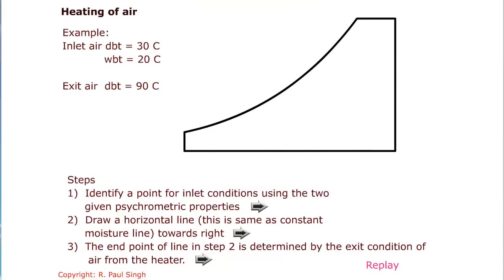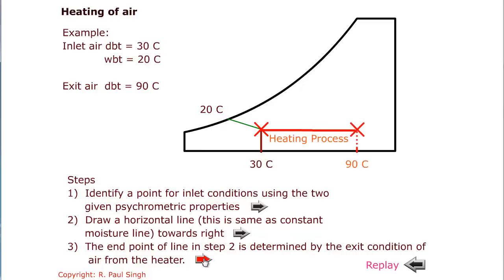Let's look at some animations. In the case of heating of air from 30 degrees C dry bulb temperature and 20 degrees C wet bulb temperature, we identify a point and then follow a horizontal line to the final exit air temperature of 90 degrees Celsius. Thus, we have identified the horizontal line and the initial and exit conditions for the heating process.